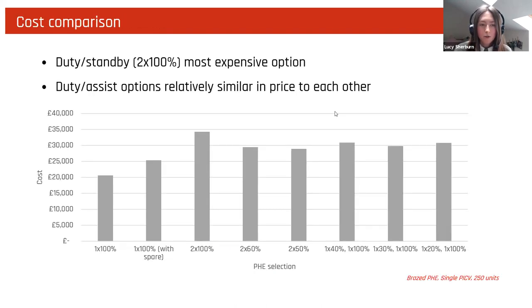please. I then looked at cost comparison. As you might expect, the duty standby provided the most expensive option. And the duty assist options are relatively similar in price to each other. There wasn't one that was significantly more or significantly less expensive. This was for the brazed plate heat exchanger with a single pick valve.